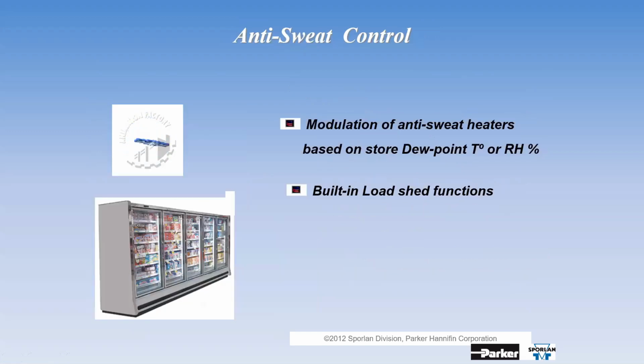Anti-sweat is another thing we can do, based on either the dew point calculation or the relative humidity. Built-in load shedding is there for the anti-sweat control too. Why? Because old school, keeping the doors heated all the time costs, on average, anywhere from $300 to $400 per door per year if left on 24/7. So with anti-sweat modulation, we pulse the anti-sweat based on how humid the store is, saving a lot of energy.